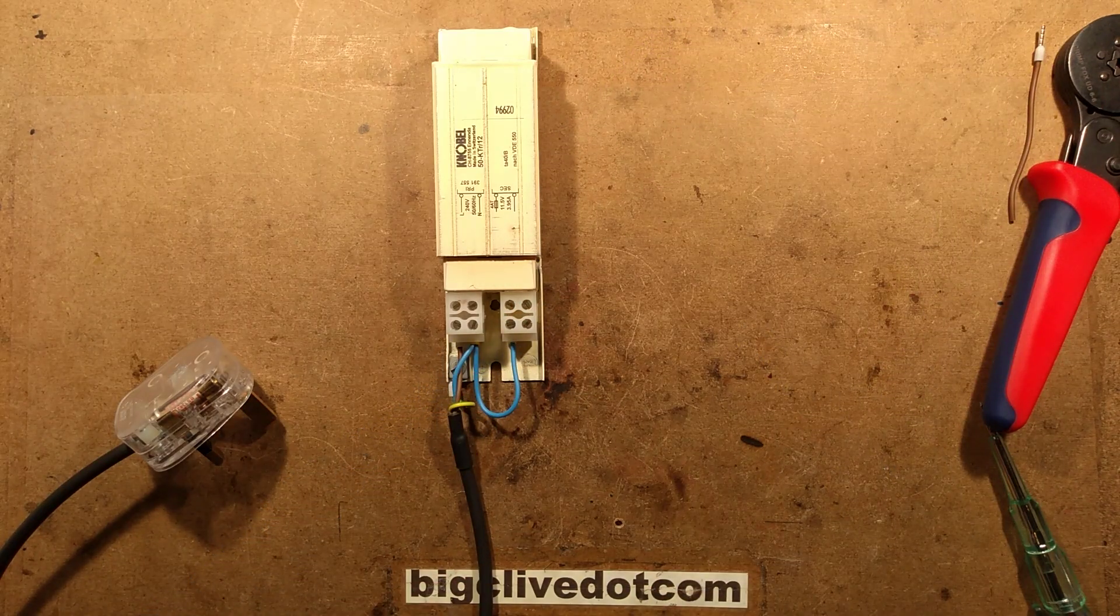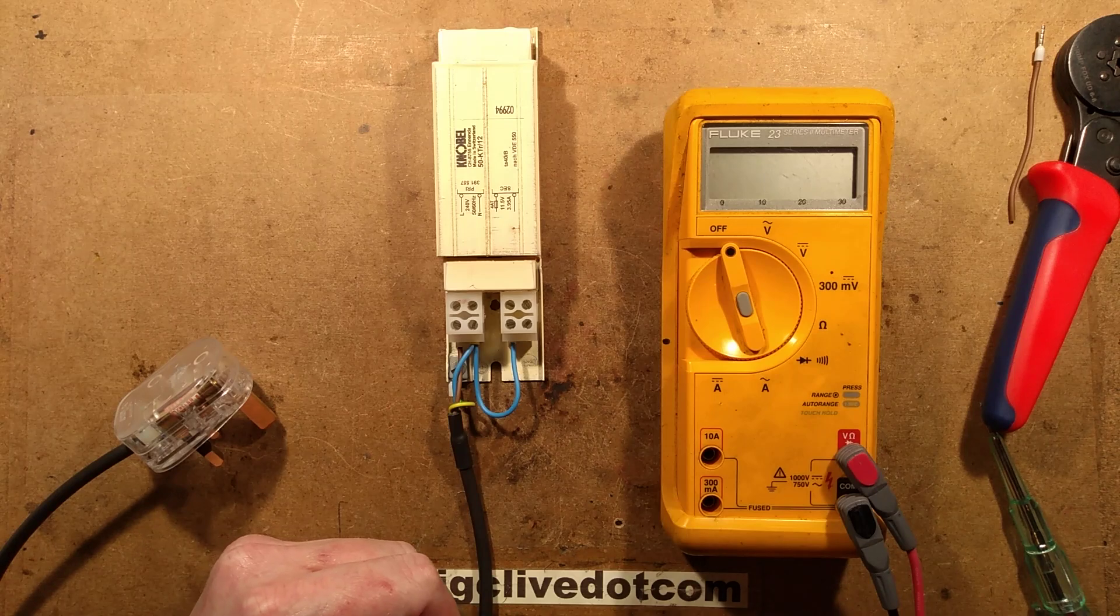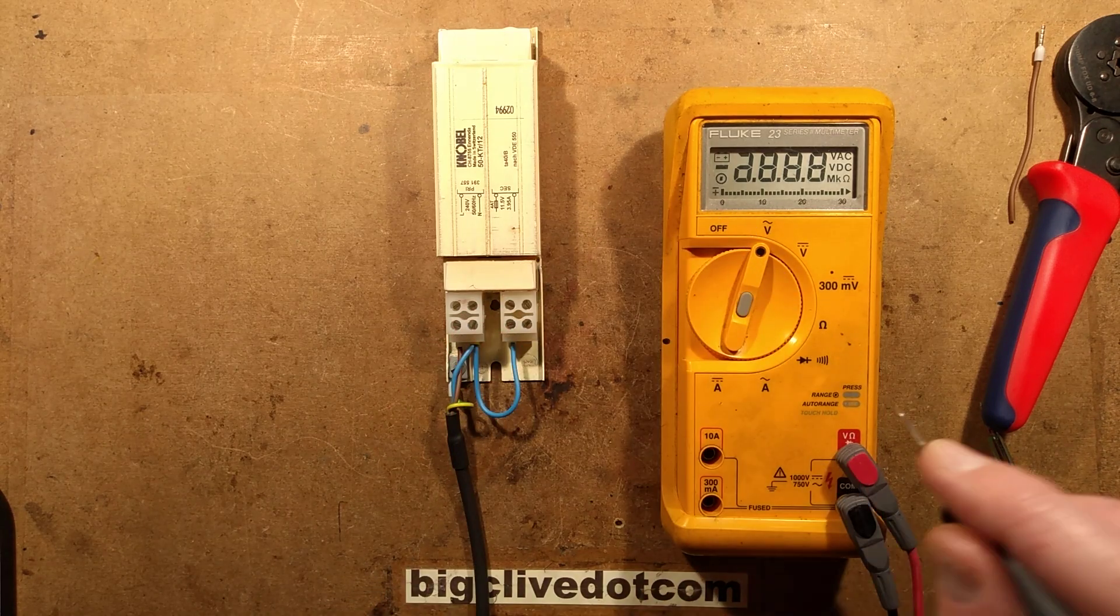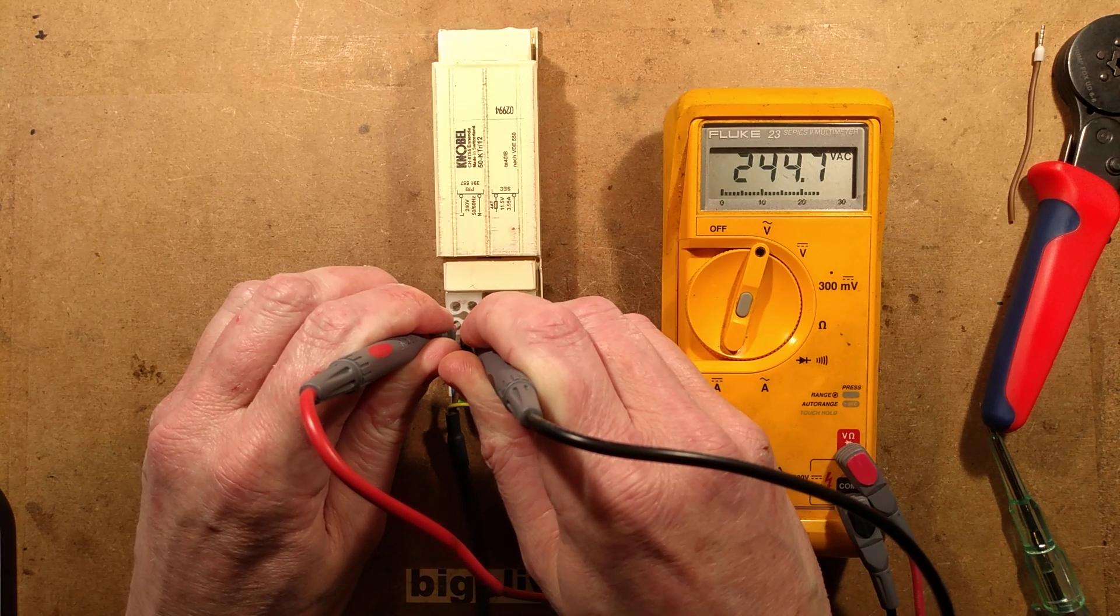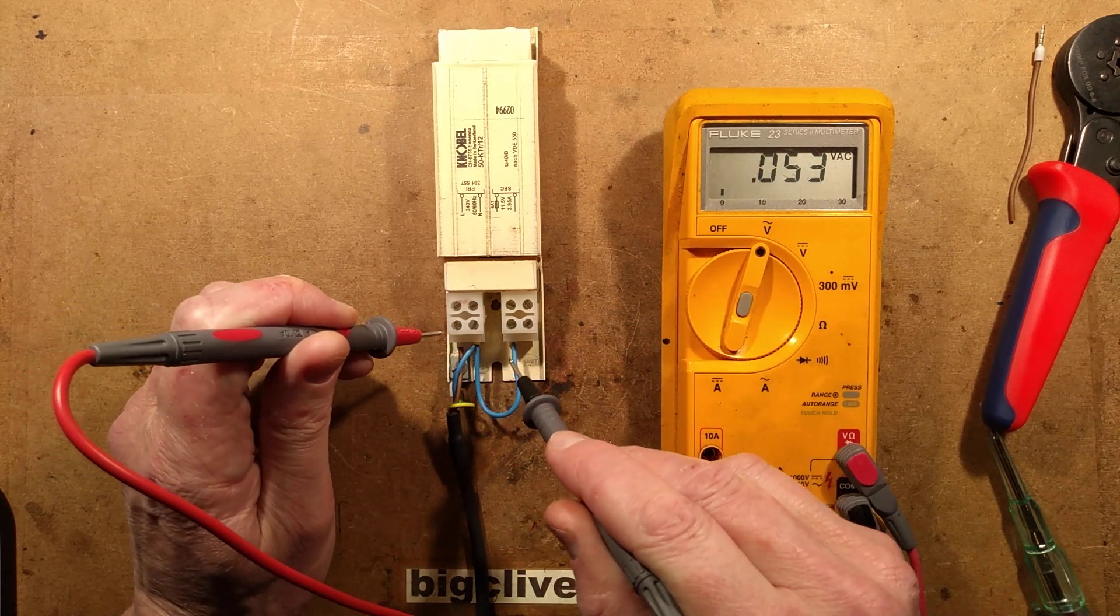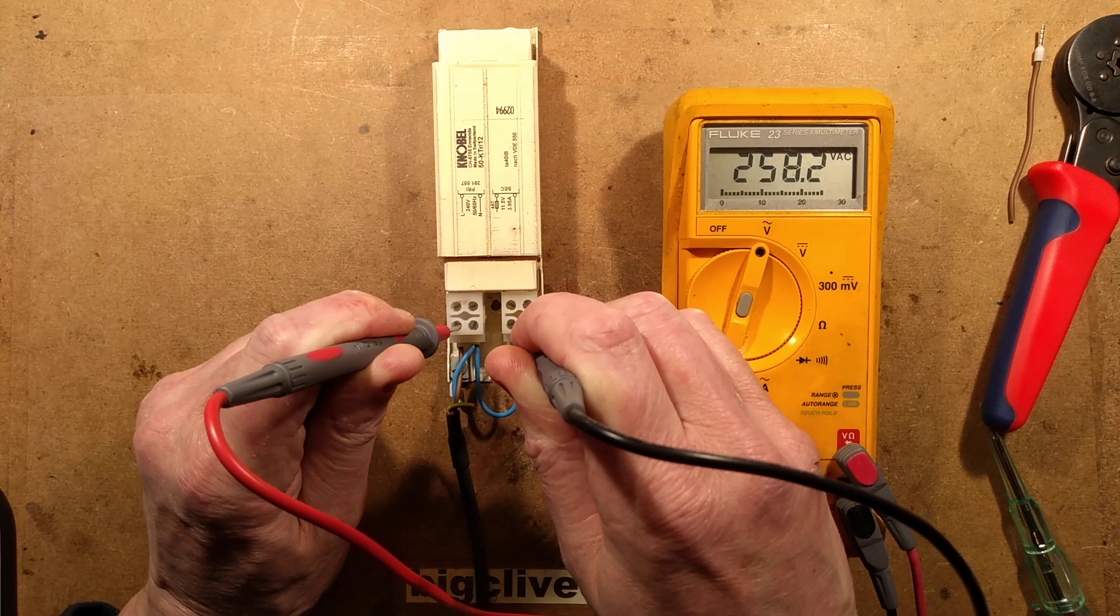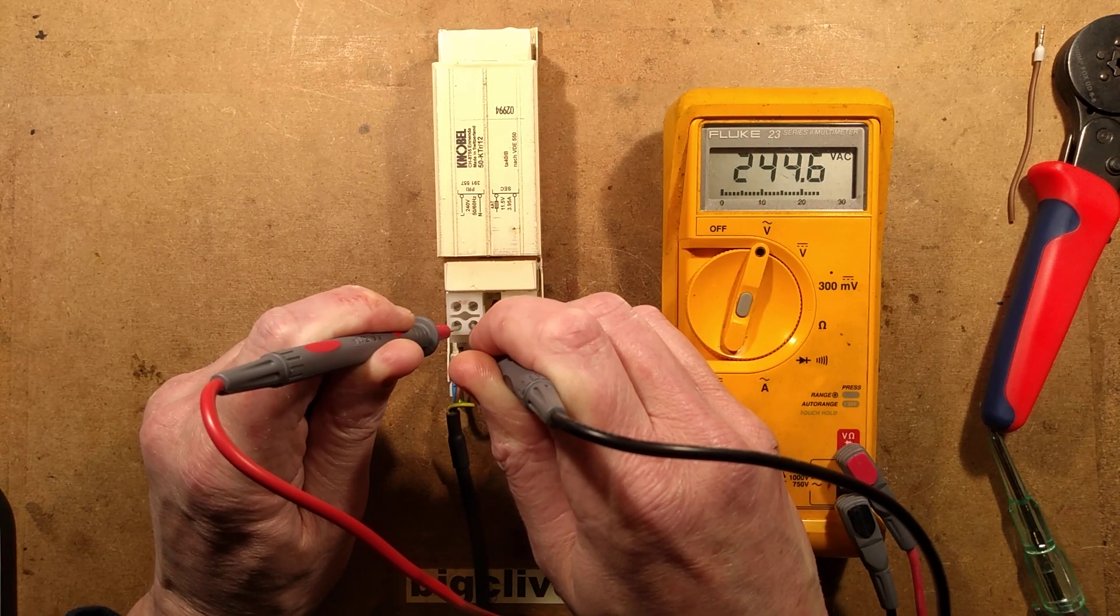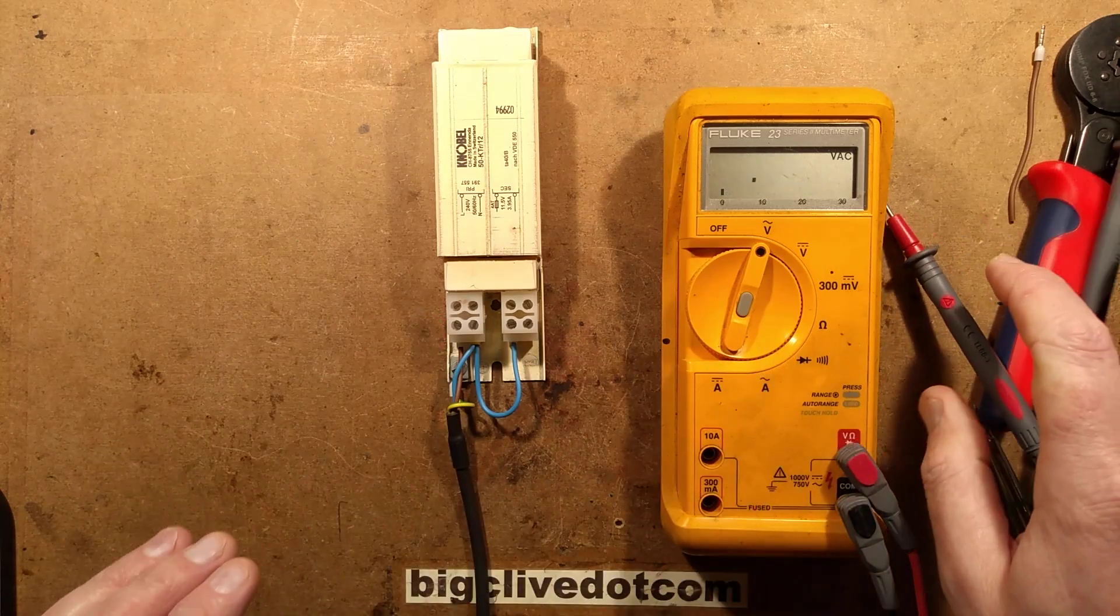And to test this, I'm going to bring in the proper, just since I'm doing all sort of mains electrical stuff, let's bring in the daddy meter, the fluke. It's bigger, it's bolder, it's rougher, it's tougher. In other words, sucker, there is no other. It's the domimeter. So I'm going to turn that on and I'm going to put this across the input supply and show you the voltage at the moment, which is just short of 245 volts. The output, open circuit with no load on it is about 13.5 volts. If I then go, because I've looped the neutral through this, so this winding is now in series with neutral. If I go from the live here to the other side of this winding, it's showing 258 volts because it's added that output voltage about 13 volts onto the original voltage, which was about 244.6 plus the secondary voltage is giving me 258 volts. So that would actually boost the voltage up.